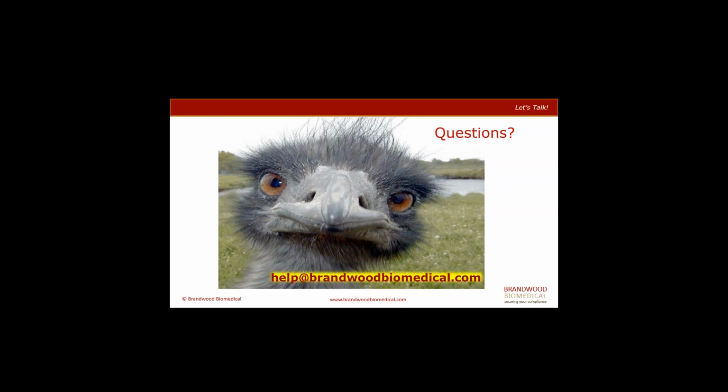Okay, from Chris Kai-Young. Does the combination of verification automatically validate the device for its intended use? Or is it typically required to conduct validation separately on top of verification? Good question, Chris. It depends on what is being verified or validated. In quality system regulation speak, if something can't be verified, then it needs to be validated each time.